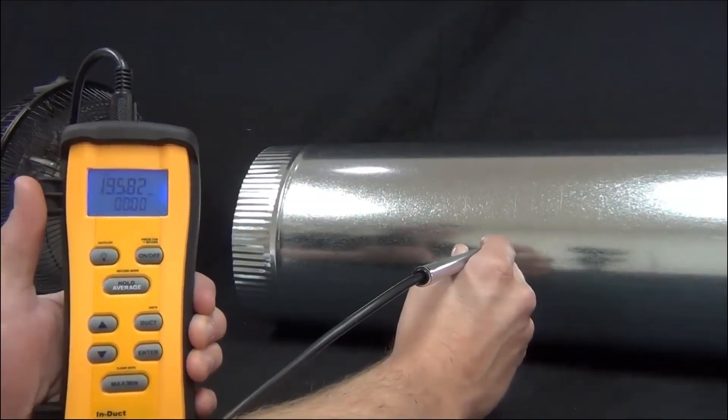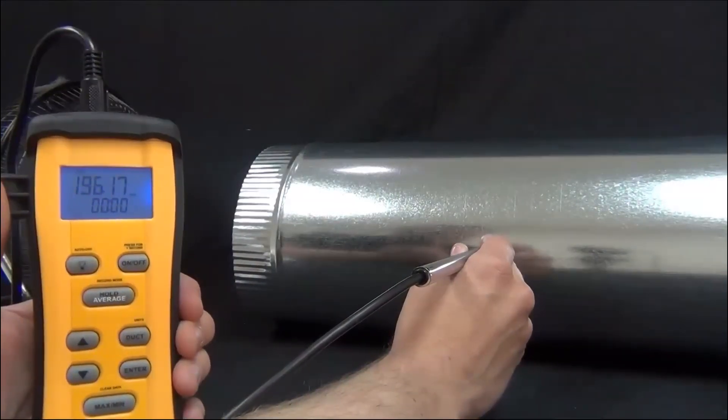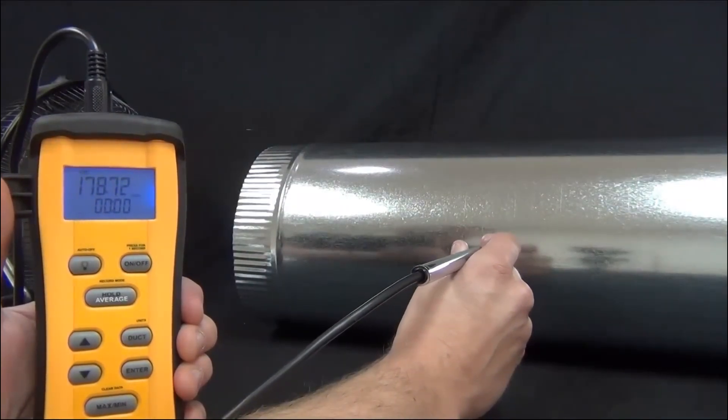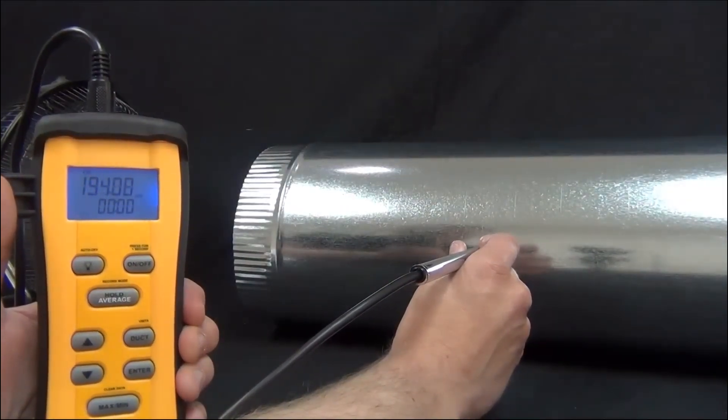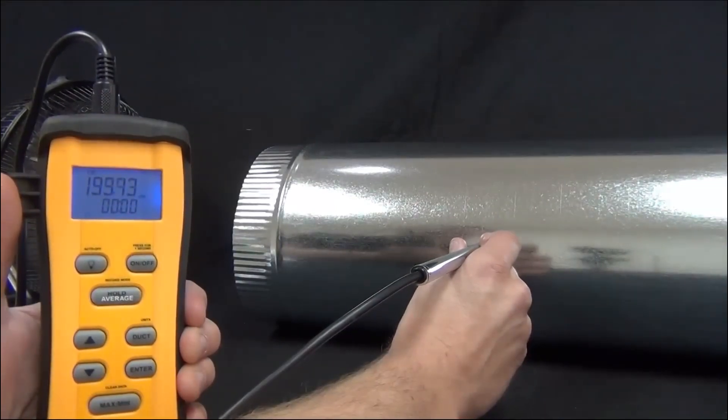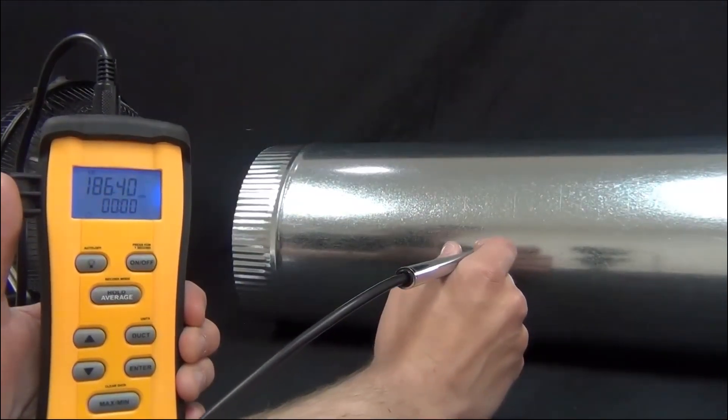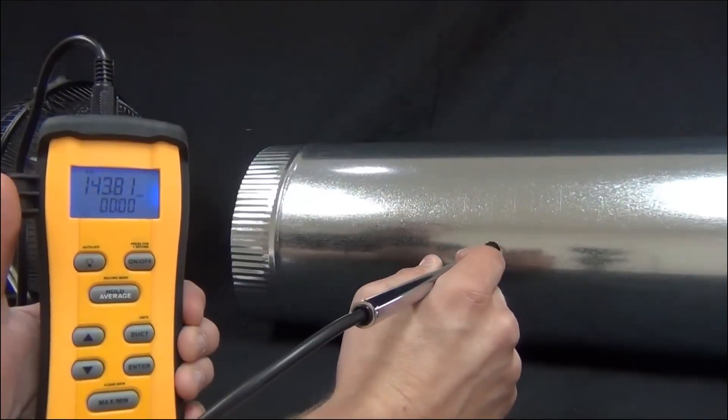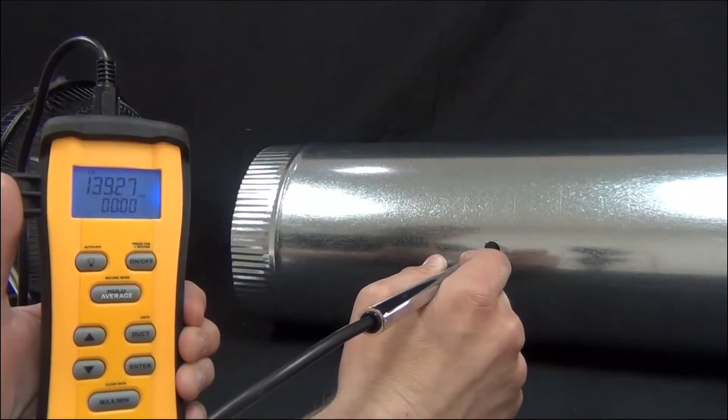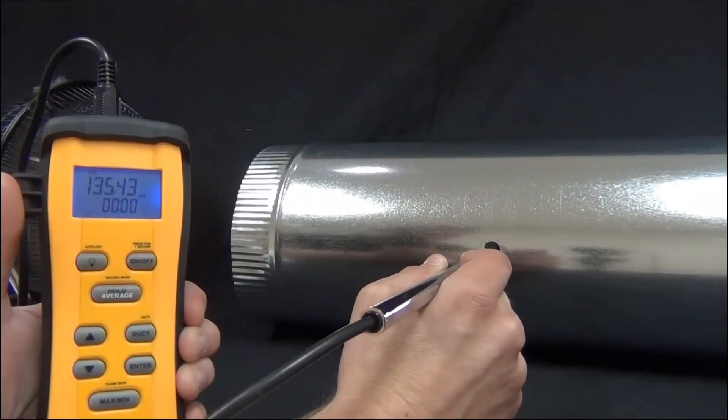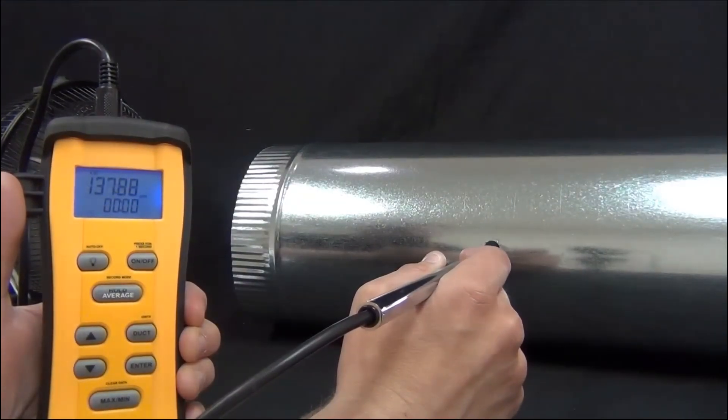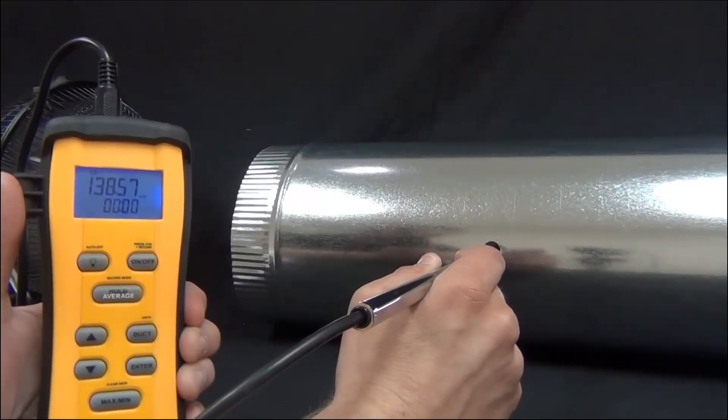Now what you'll see is as I just read it live, the CFM is dramatically different on the edge of the duct versus in the middle. So we're getting 195 CFM on the edge of the wall. And as I move it towards the middle, right in the middle, it's at 120, 130 in that range. So it's a pretty big difference. So what we want to do is make sure that we get an accurate average across the duct.